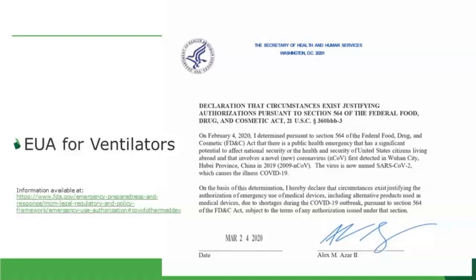Now, also, as part of these authorizations, you cannot promote an authorized product as, quote, safe or effective, unquote, which is also kind of a novel proposition for many people on this phone call who are not used to hearing this. And obviously, once again, let me give the caveat, read your own authorization, because each authorization is different. I'm just generalizing here. But the authorizations also have all sorts of details on what can be put into promotional materials. For example, in the authorizations for ventilators, it says that, quote, this ventilator has not been FDA cleared or approved, unquote. That has to be put in promotional materials, which frankly sounds like the dietary supplement statements.